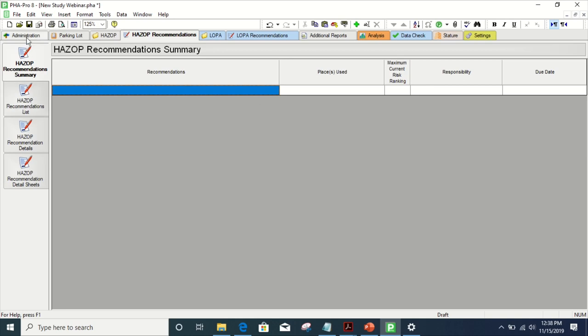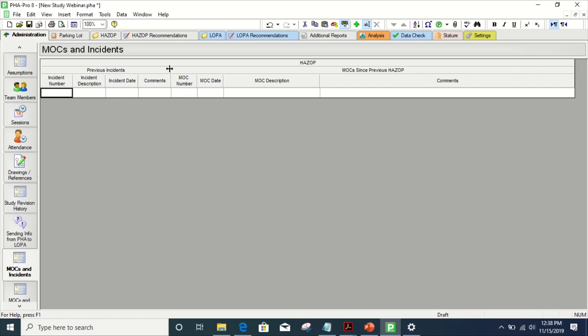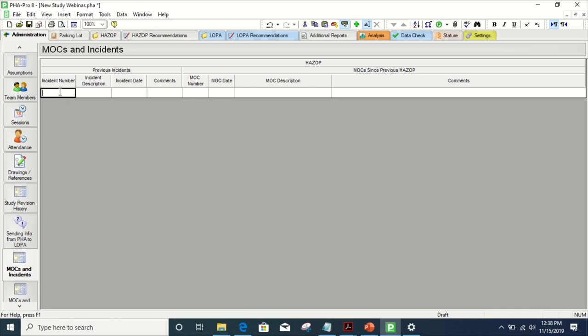Another thing that should be tracked within your PHA-Pro file is MOCs and incidents. You don't have to track it in here — Excel can do a fine job and people can all access it, and here you'll have your license where only one person can access it at a time. But it's good to keep it with the PHA so that you can figure out the previous incidents, see what went wrong previously and how you're currently mitigating it, and your MOCs since the previous HAZOP — what has changed and what you need to look at that's new within your study. You can be doing a revalidation and really only need to look at your MOCs, revalidate the other scenarios, and take a closer look at what has changed. But this isn't part of the template coming into it, so let's look at how I made this tab and how you can make it as well.